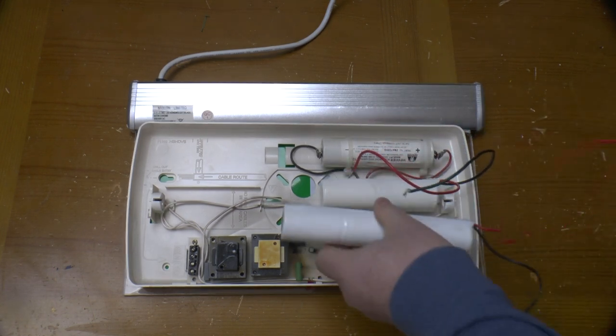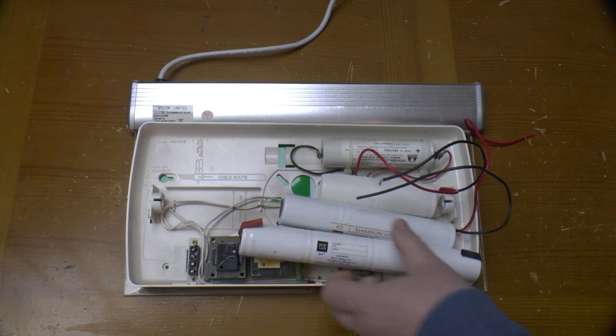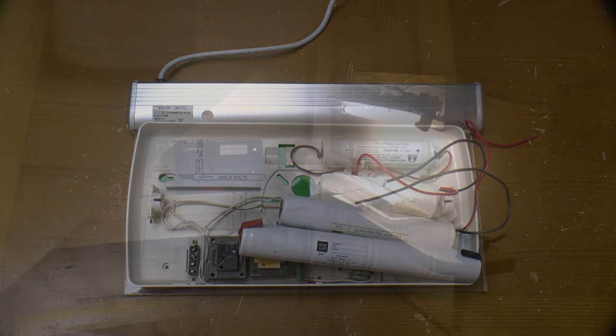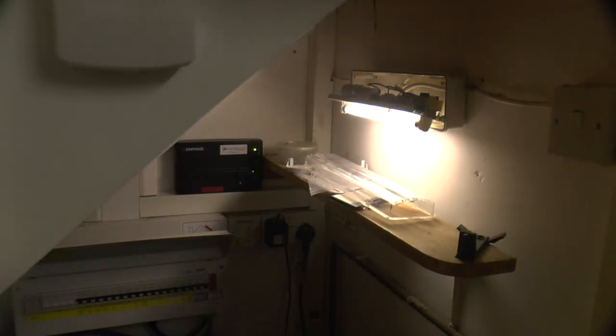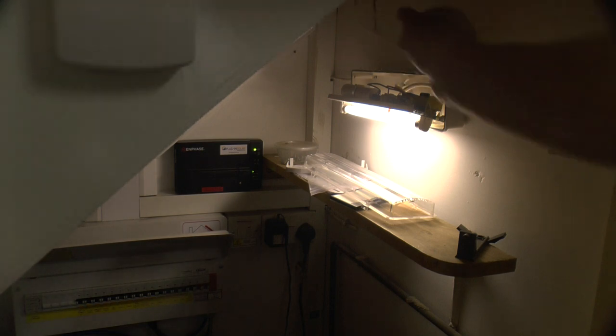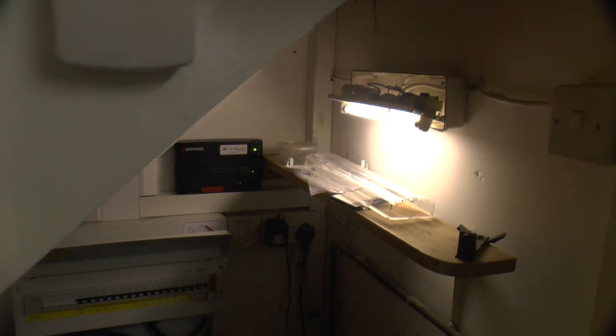Here are 2, 3, and 4-cell sticks for various lights. I've got an emergency light fitting under the stairs by the consumer unit. That's a 2-cell unit as well, still working fairly well despite being over 15 years old, although it falls short of the 3-hour mark these days. This one is a maintained switched fitting, which has two supplies. One permanent to keep the battery charged and detect a power failure. The other switched, so the light can be used normally.